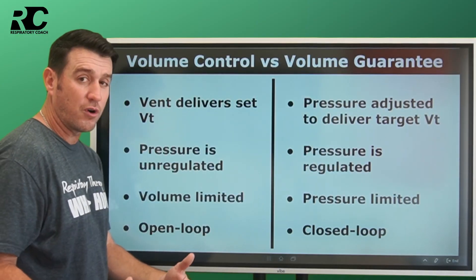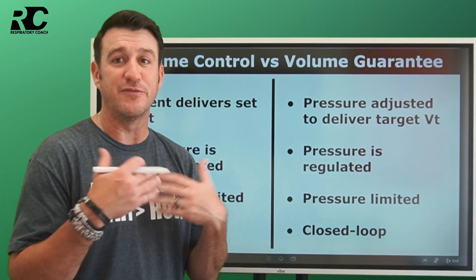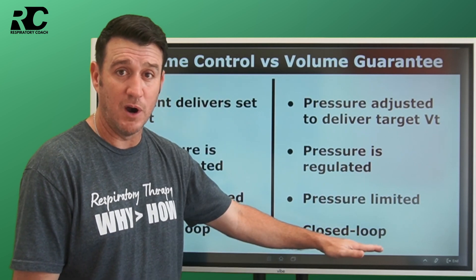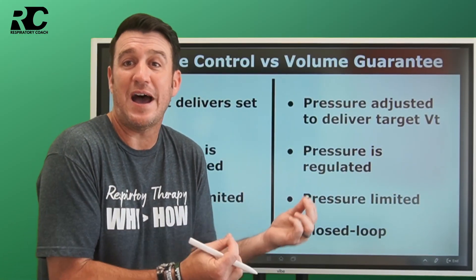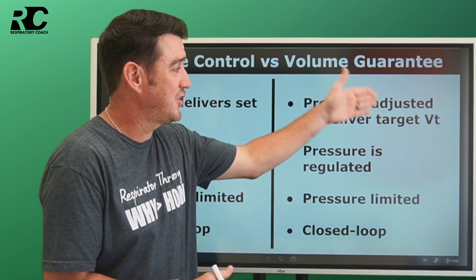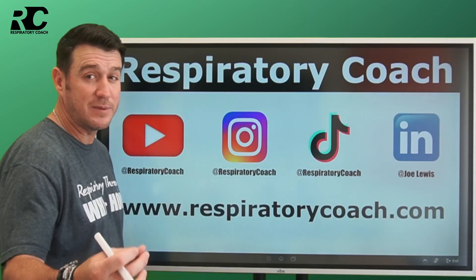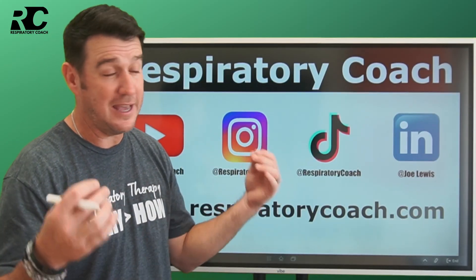Open loop mechanical ventilation — the vent doesn't talk to itself; it does what you tell it to do. Volume guarantee is a closed loop mode — the ventilator talks to itself: volumes too high, turn the pressure down; volumes not high enough, turn the pressure up. It adjusts itself to reach that target tidal volume. That is volume control versus volume guarantee in a nutshell.